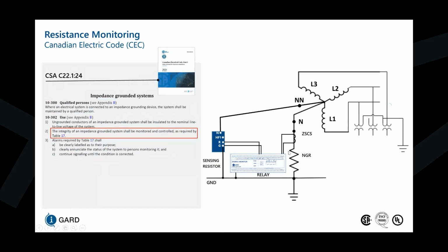Now, when the competitor is using strictly a DC-only injection through this path, they see these inductances as short circuits, and they could have issues with YY connected PTs where the primary is grounded because their DC signal leaks out into the system and finds this alternative path to ground. These PTs here have a very high AC resistance, but their DC resistance is very low, such that this signal can get through and falsely claim that it's checked the NGR when it hasn't, or falsely indicate that the NGR is in a fault condition.